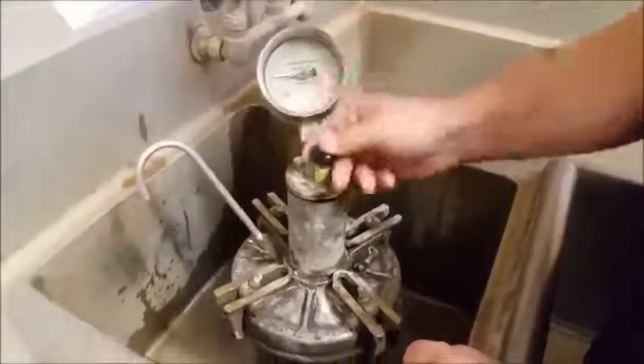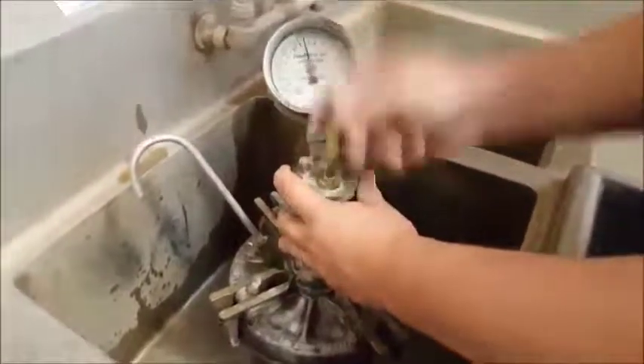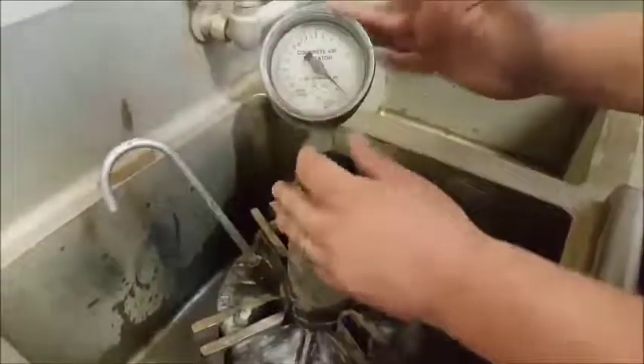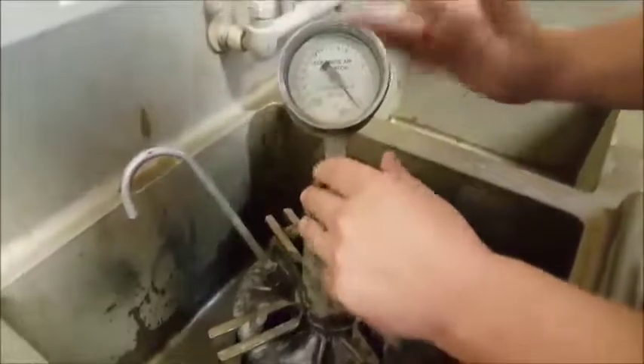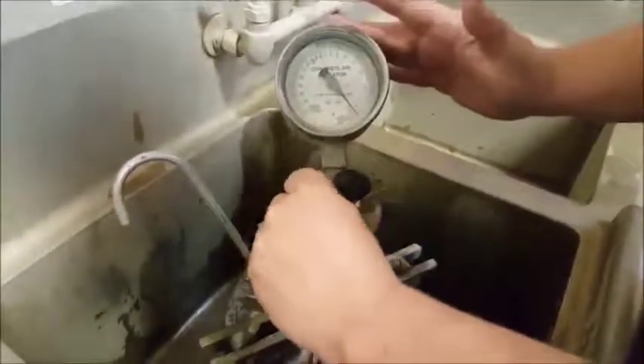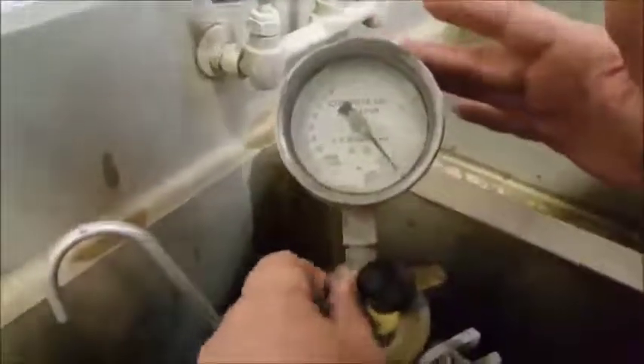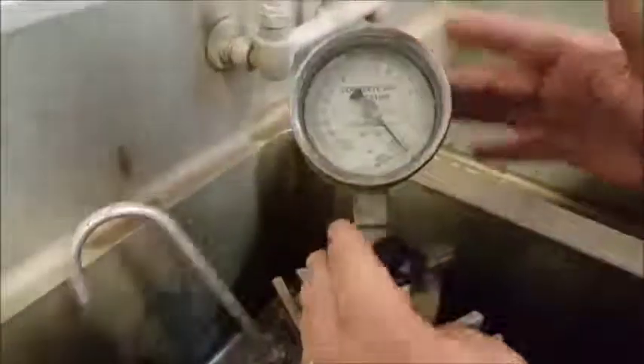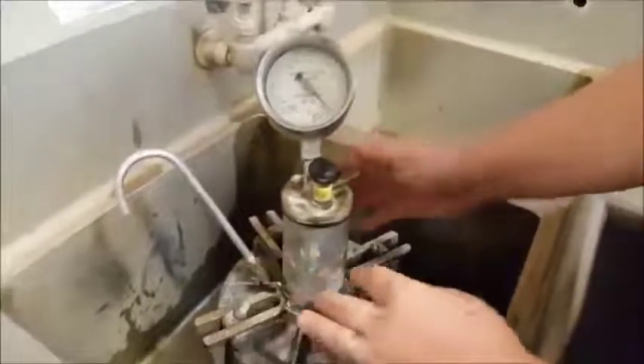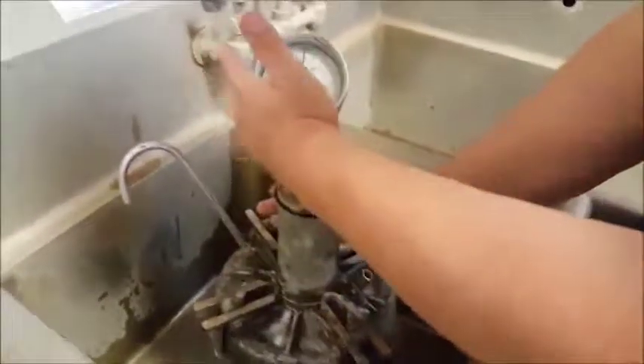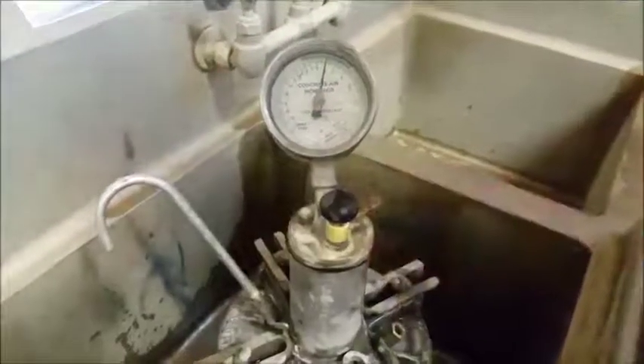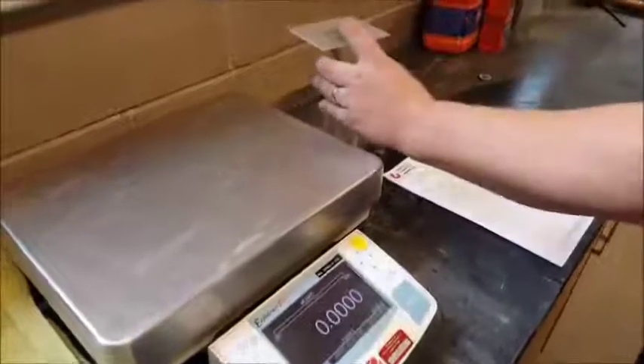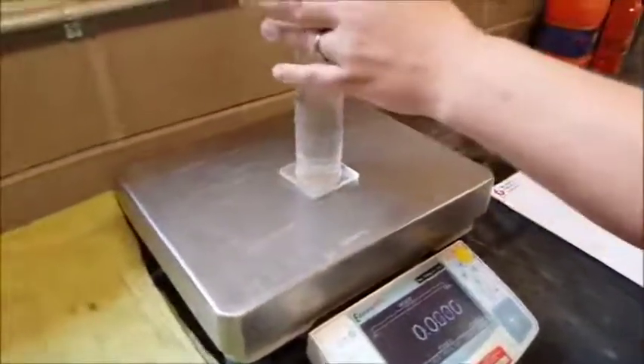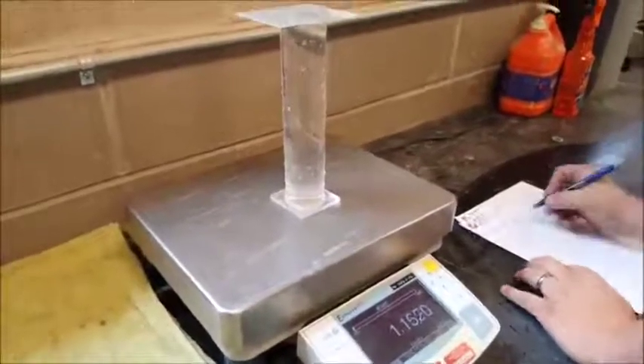Next, we're going to pump this back up to our initial pressure of 2. Overshot a little bit there, so we'll let a little pressure off. Okay, close the petcocks and release the pressure. We're hoping this ends up on about 5. That looks pretty good. Next, we're going to weigh the calibration vessel filled with water and record that information.